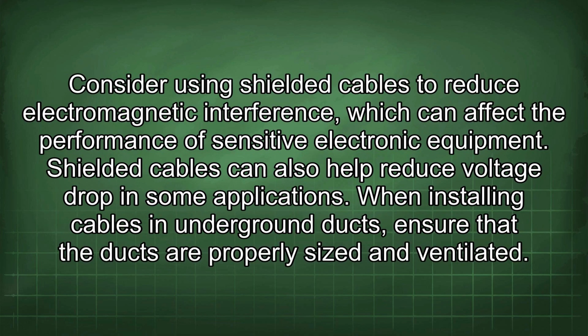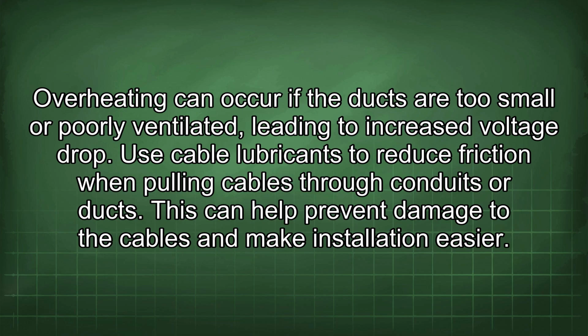Consider using shielded cables to reduce electromagnetic interference, which can affect the performance of sensitive electronic equipment. Shielded cables can also help reduce voltage drop in some applications. When installing cables in underground ducts, ensure that the ducts are properly sized and ventilated. Overheating can occur if the ducts are too small or poorly ventilated, leading to increased voltage drop. Use cable lubricants to reduce friction when pulling cables through conduits or ducts. This can help prevent damage to the cables and make installation easier.